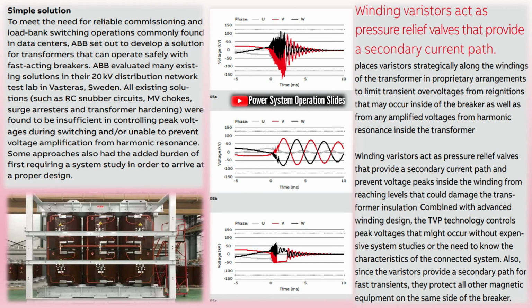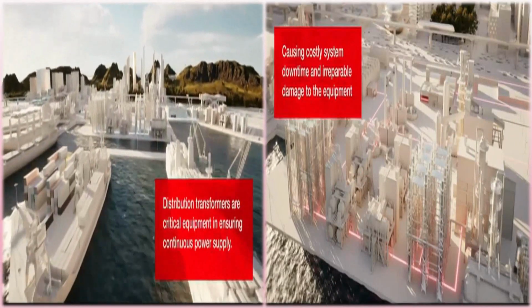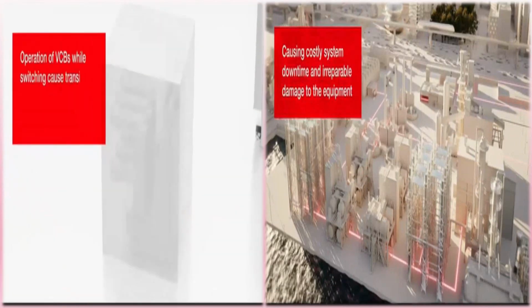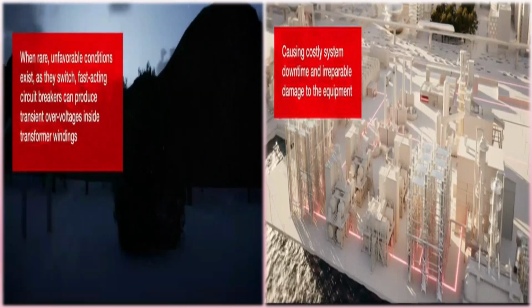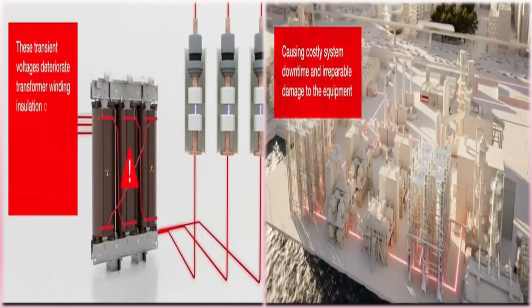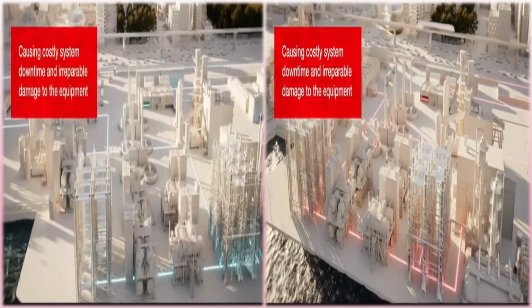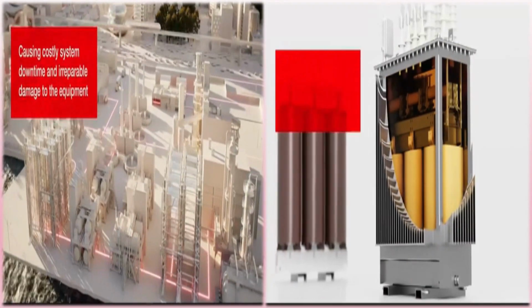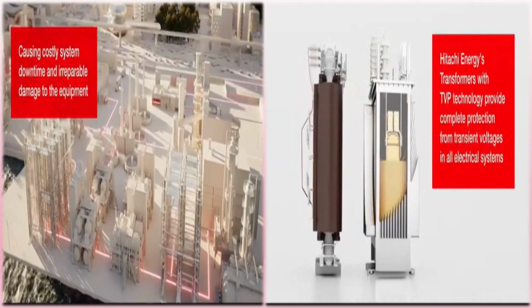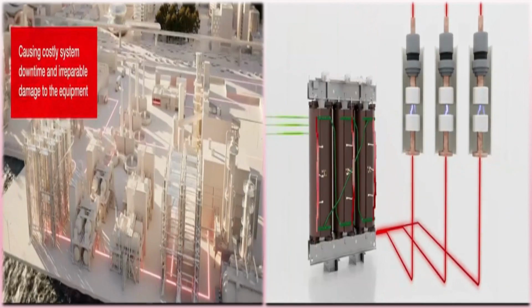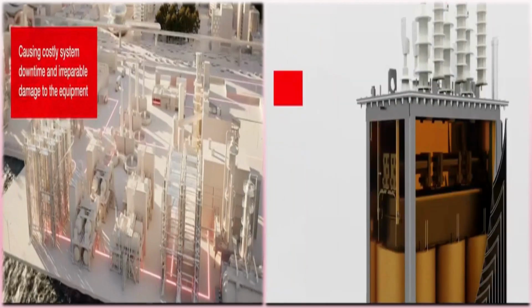In comparison to all the conventional transient protection measures available currently, Hitachi ABB Power Grids' transient voltage protection (TVP) technology for transformers serves as a holistic solution that efficiently controls internal voltage peaks with minimal impact to the overall transformer design. Hitachi ABB Power Grids developed this technology so that distribution transformers can safely operate with vacuum circuit breakers in any network without the need for a system study. These transformers are specifically engineered using winding varistors that are strategically integrated with the transformers to protect them from transient surges. Winding varistor-based protective systems provide a simple solution to the rather complex problem.